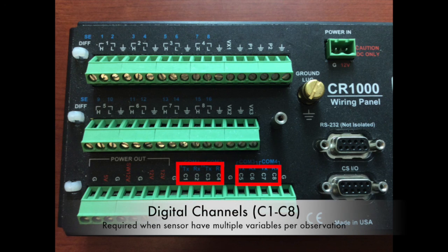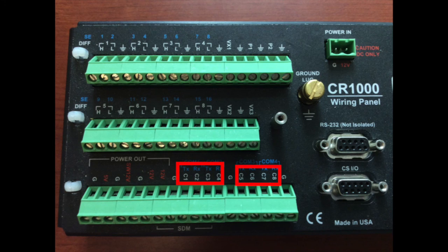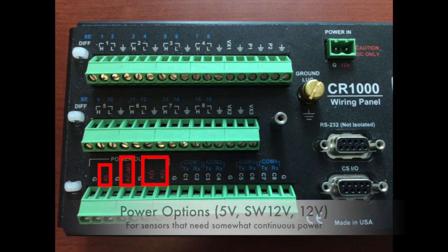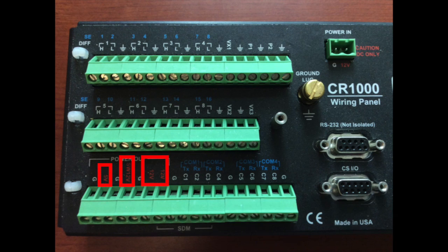Then you have digital channels, located on the very bottom, C1 through C8. These digital channels are able to report back multiple parameters from the same sensor. A WXT520 is a perfect example — one output that sends back all six parameters. We also have different power outlets on the left side: two continuous 12-volt channels, a switched 12-volt channel, and a 5-volt channel. The 5-volt channel is for precipitation, and the switched 12-volt is for sensors that need power turned on and off.